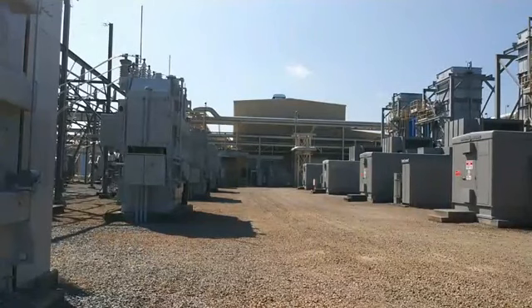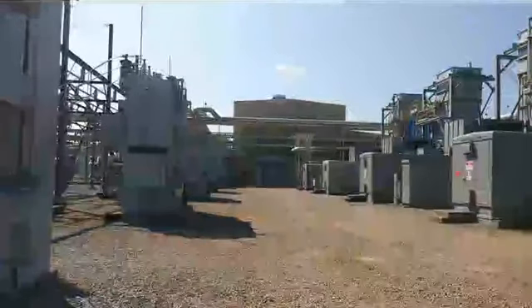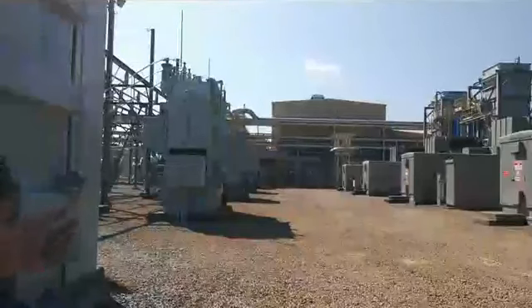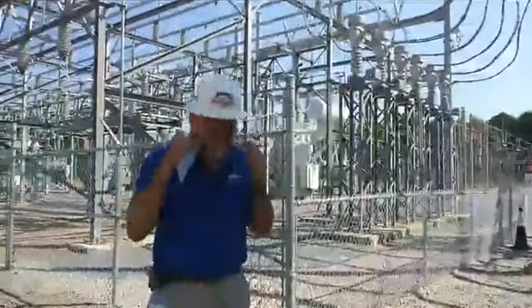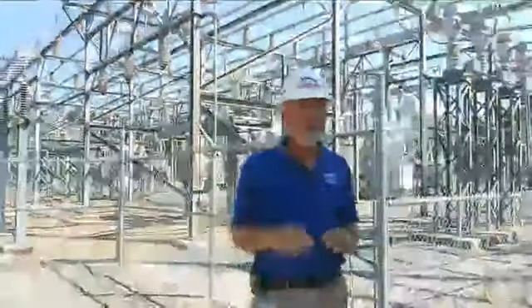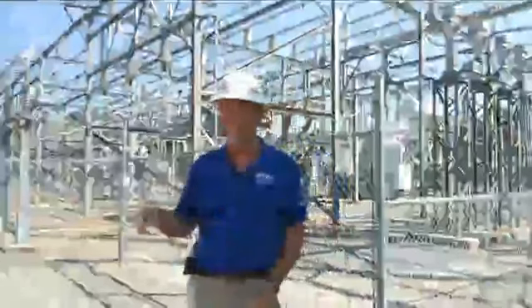We have another question: is this the gas turbine powered peaking facility behind Cargill? Yes — gas turbines, correct, and we are near Cargill. This was built as a peaking plant, meaning you only run during peak hours. A nuclear plant is what they call a base load plant, a coal plant is an intermediate base load plant. You hear in the news that the EPA is doing away with coal — what they're building today to replace coal plants are combined cycle plants just like we have here, just newer technology and a little more efficient. The biggest advantage for us is that we have that number two fuel backup. It's more expensive than natural gas, but in the winter when it's 7 degrees outside natural gas is not available. We can light up on fuel oil and make energy without relying on the gas.